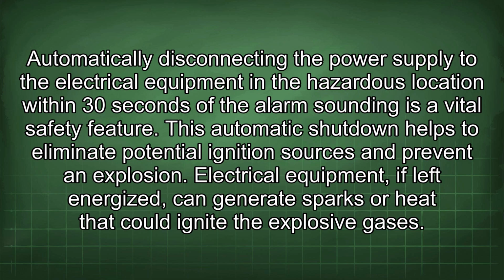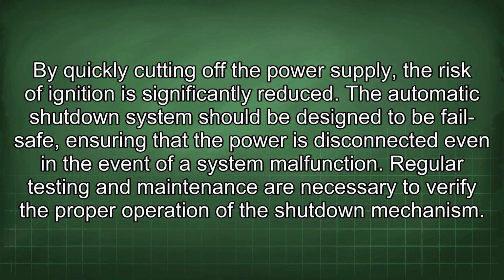Electrical equipment, if left energized, can generate sparks or heat that could ignite the explosive gases. By quickly cutting off the power supply, the risk of ignition is significantly reduced. The automatic shutdown system should be designed to be fail-safe, ensuring that the power is disconnected even in the event of a system malfunction. Regular testing and maintenance are necessary to verify the proper operation of the shutdown mechanism.